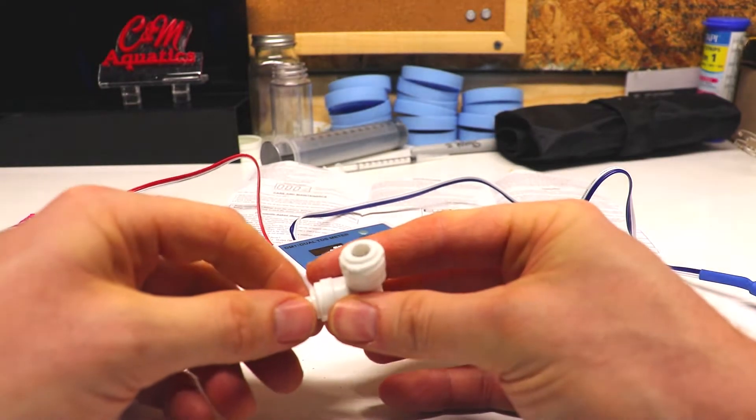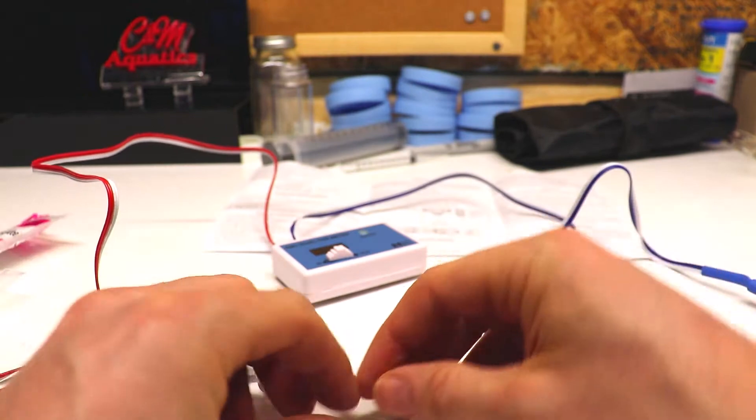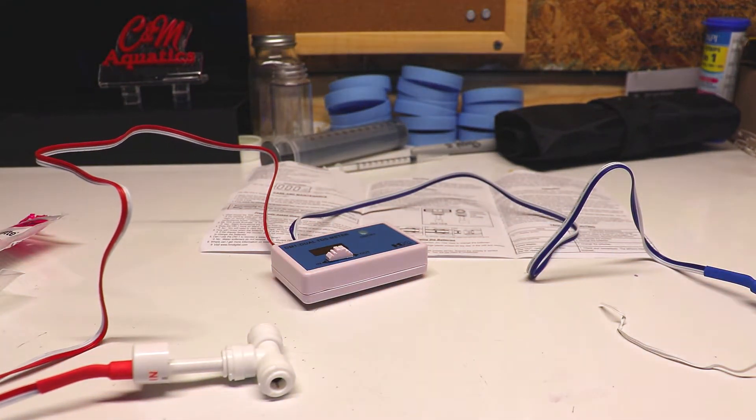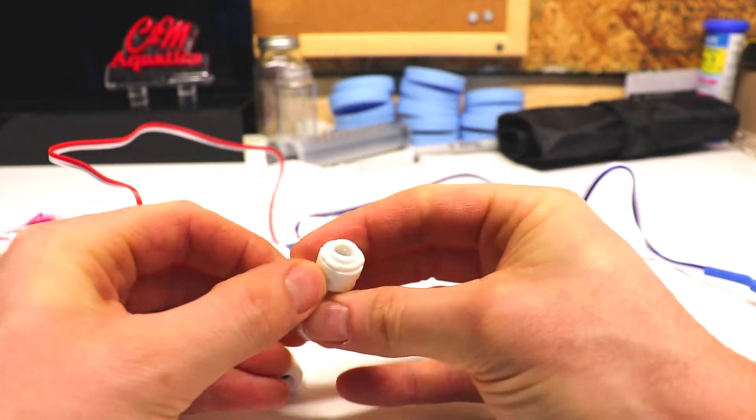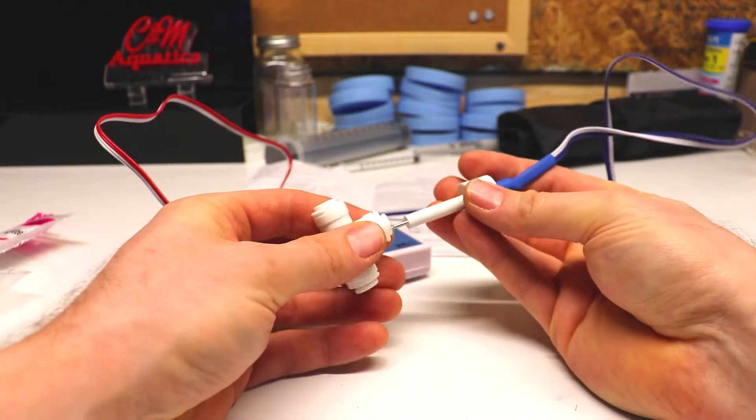When you're pressing in your probe, you want to press it in to make sure you feel it pop and press in securely, and pull back on it to make sure it doesn't come out, because that's where you're probably going to have your best chance of a leak.